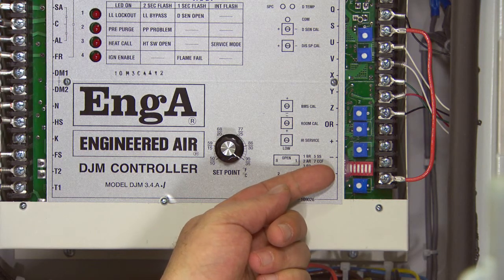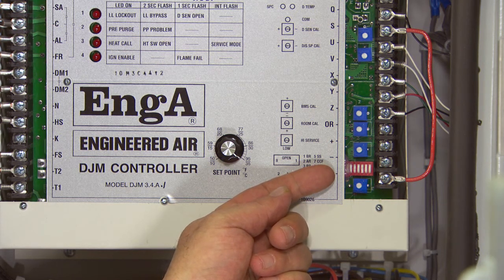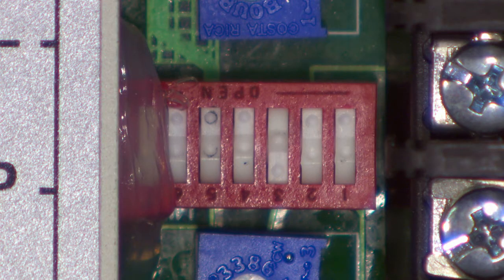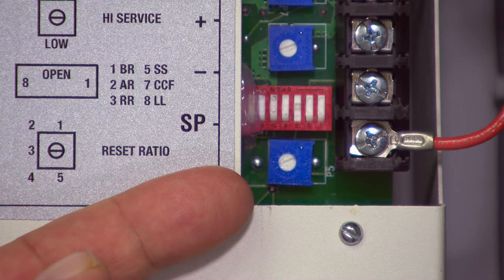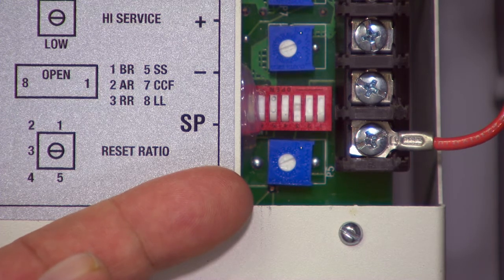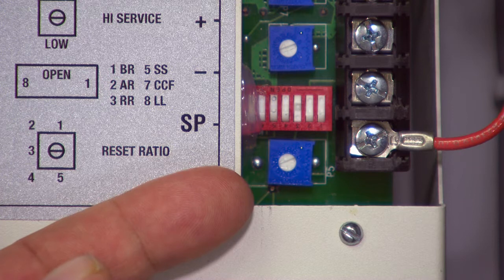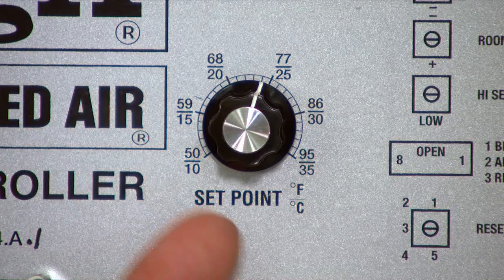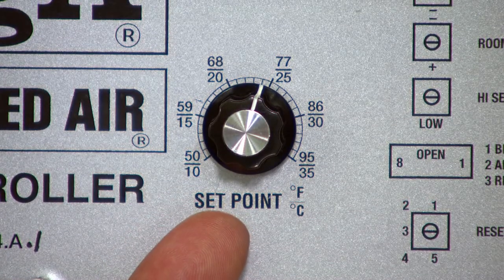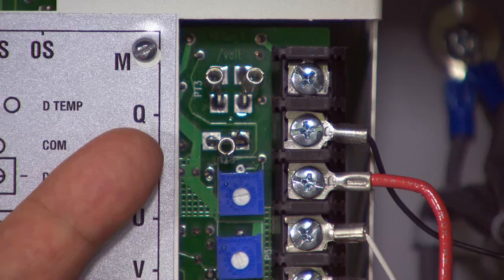The dip switches provided on the board allow the user to activate various reset configurations, initiate the service mode for combustion setup, and the maintain mode for combustion fan, and provide low-limit protection on the discharge air to the space. The calibration potentiometers on the DJM-3 board are used for initial setup and should not be adjusted unless you are familiar with their operation. The set point knob on the face of the DJM-3 is for local control set point. Finally, the set point and discharge temperature can be read as voltage on the readout pins.